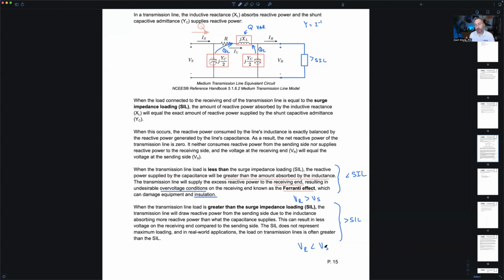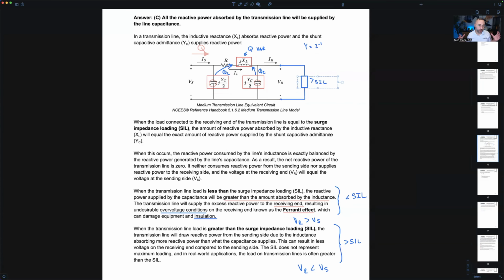Interesting. Now, a couple of things we want to point out. In real life, do we always get a perfect match? Do we get that perfect surge impedance loading on a transmission line? Not really, right? In real life, we build a transmission line, we try to future-proof it as much as our dollars will allow, as much money as we have in the project. It's going to be cheaper to build it with extra capacity than it is to go back and upsize it, right? So rarely ever do we get a perfect match on the load to equal the surge impedance loading. Your surge impedance loading does not represent maximum loading. And in real world conditions, a lot of times the load is going to be greater than the surge impedance loading, right? We're adding more and more and more power. More homes are being built. More factories are being built, right? Typically, the demand of our electric grid is outpacing what we had built 10, 20 years ago.